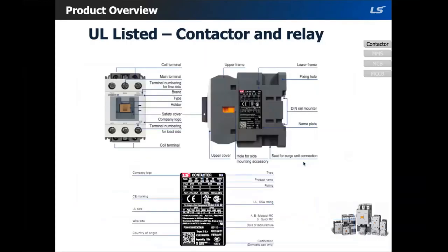So this is the front view and then the side view of the contactor with the nameplate. So on the nameplate, you can see UL size, NEMA size, and wire size, and you can also see the date of manufacturing and all the certifications that you will need for inspectors.